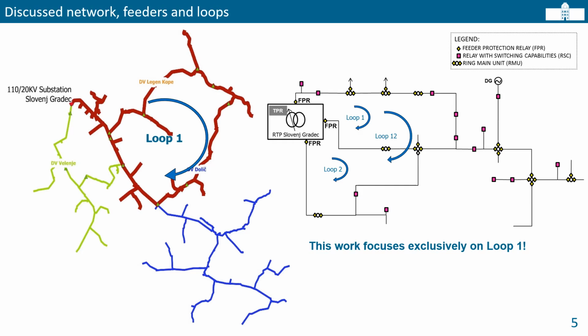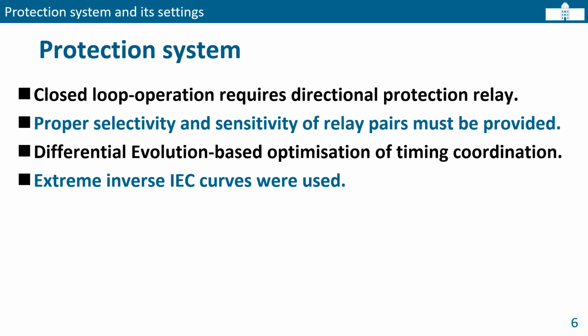On the left-hand side, we have a presentation of the network and these two feeders that build the loop number 1. This is the graphical information system presentation, and another, the schematic presentation, is on the right-hand side, where you can see the loop number 1. Both feeders are supplied with feeder protection relays marked with yellow color, and in addition some other relays marked with the red squares are introduced in the loop. Some of them are directional. Our observation is focused only on the loop number 1.